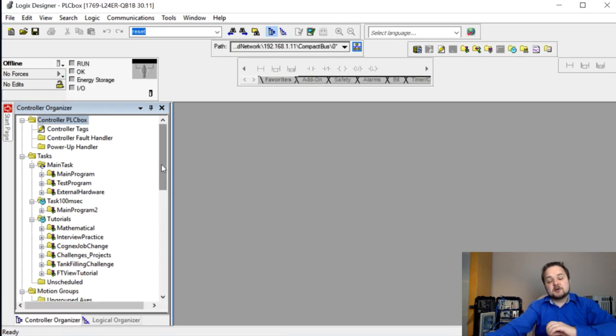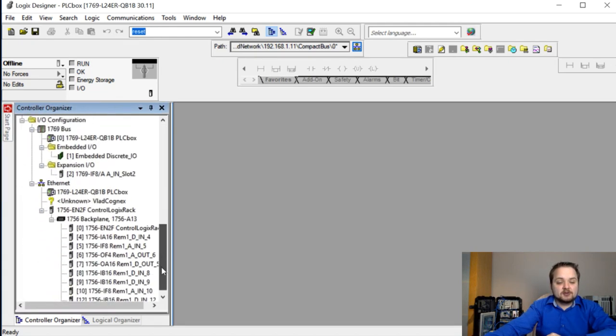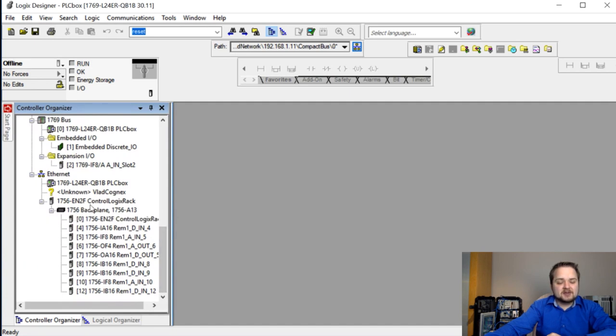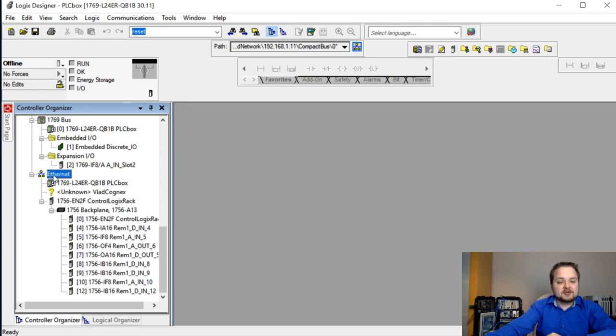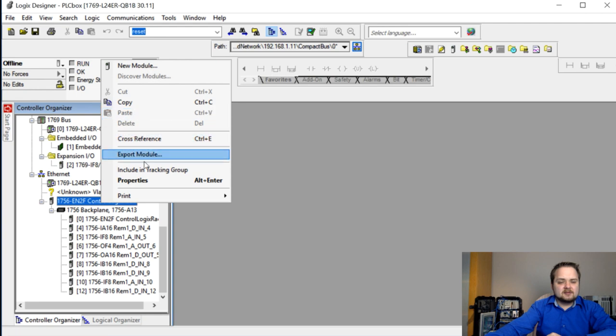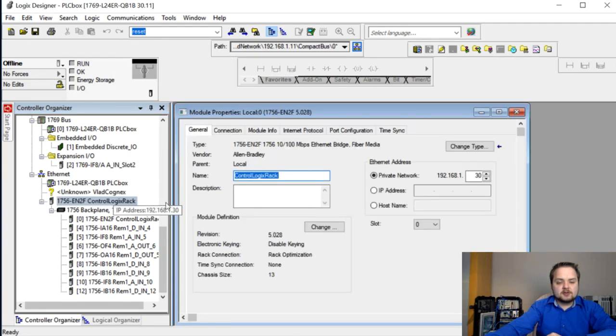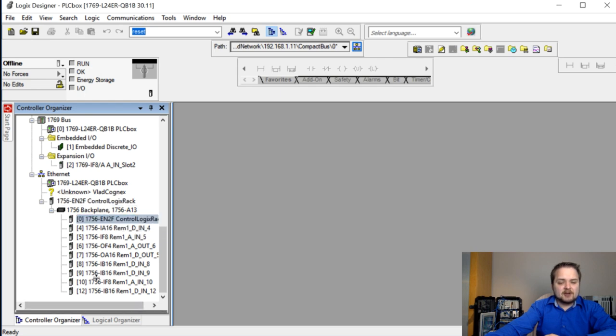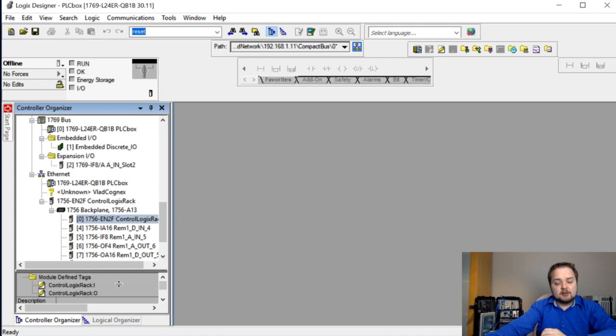The first thing we need to set up is the network path between the two processors. On the CompactLogix side, scrolling down into the ethernet rack, I already have some communication path set up for the ControlLogix rack. To add this, you right-click the ethernet node, select 'New Module,' and add the EN2F card - that's the ethernet bridge. I had to set this up previously to read tags coming through that module.